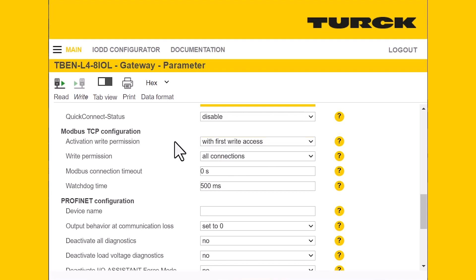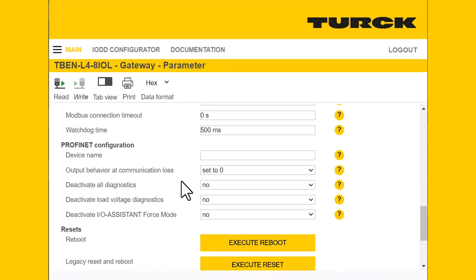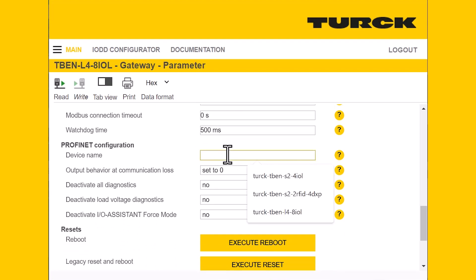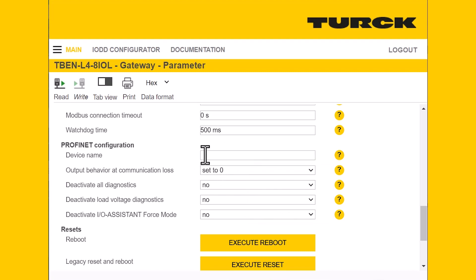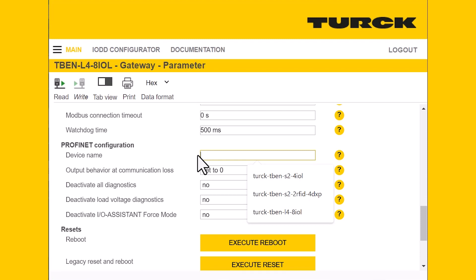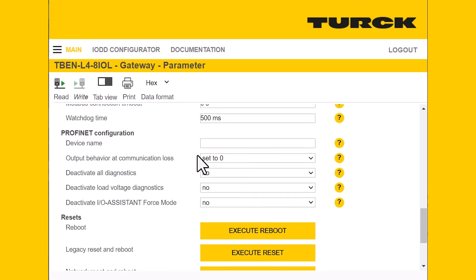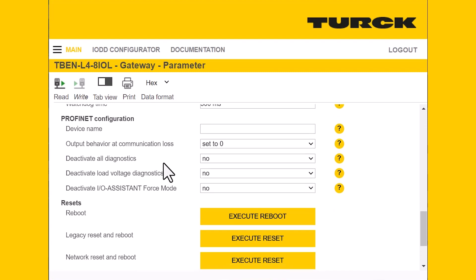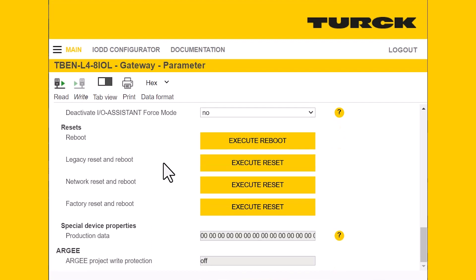We can change our write permissions under the Profinet configuration section. This is where you'll put in your Profinet device name — that's a common issue people run into, not setting the device name, so this is where you do it. You can also turn off your diagnostics, set your behavior for communication loss, and access reboot options such as factory reset, network reset, or a general reboot.